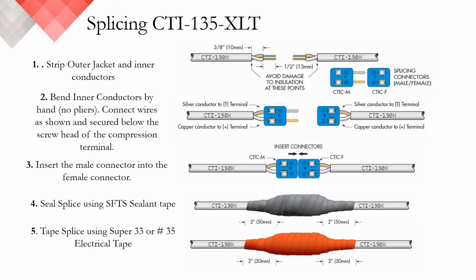Splicing our CTI series detector follows many of the same principles but uses a different compression terminal. Once again, the first step is to remove a small portion of the outer jacket as well as the heat-sensitive polymers around the metal conductors. Next, gently bend and then insert the polarity-sensitive conductors into the blue CTIC splicing connectors. One of the CTI series detector conductors is a copper color while the other one is a silver color. Our CTIC splicing connectors have matching compression terminal colors to identify and simplify polarity.